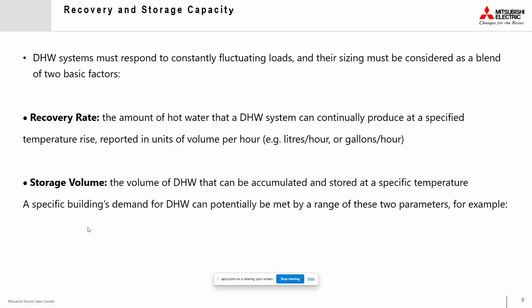So we have two terminologies used: recovery and storage capacity. Domestic hot water systems must respond to constantly fluctuating loads, and their sizing must be considered as a blend of two basic factors. Number one is the recovery rate. That's the generation capacity or production capacity of the equipment, the amount of hot water that a domestic hot water system can continually produce at a specified temperature rise. That could be in liters per hour or gallons per hour per day per person. So that's your recovery rate.